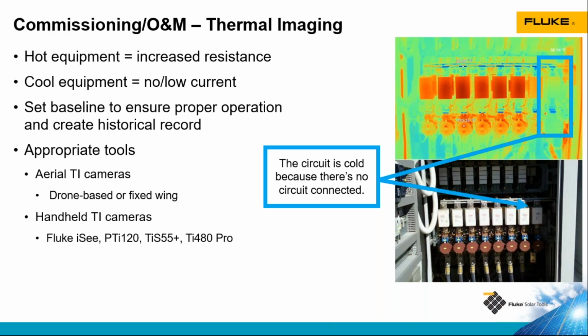As you go up in models, the resolution of the cameras increases, and the higher the resolution is, the further away you can be from a piece of equipment and still get a good quality image. So you could be outside the electrical hazard zone and still get a good image of what you want to look at.